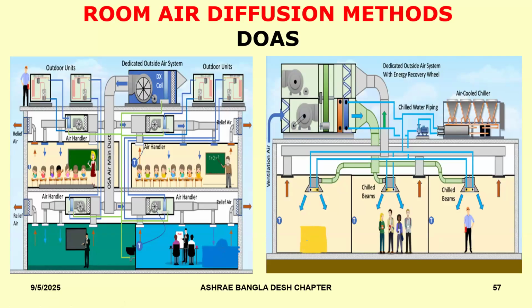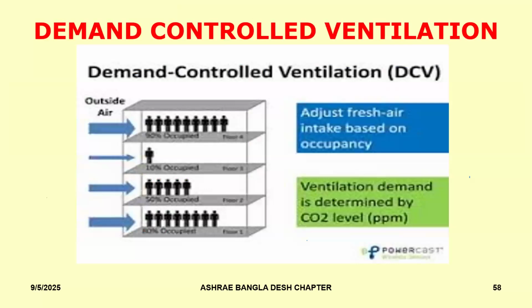So once you do your load evaluations, you pretty much know how much of it is required where. And you can have different types of, for example, here we got chill beams. So we have a dedicated outdoor air system that is bringing in the air and supplying it to the chill beam directly. Okay, so this is one method by which you can have a dedicated outdoor air system that can treat the outdoor air and admit the required quantity into each space. And we can go one better by saying, how do we actually control this?